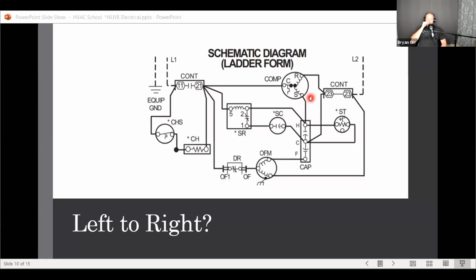In some cases, those resistances will be so low that your meter will actually ring when you're measuring leg to leg. And that doesn't mean that your compressor is always going to draw these ridiculously high currents. Because if you work Ohm's law, it will look like you're going to have 100 amps, whatever. That's only what it draws when it starts. Once that compressor gets moving and you get that inductive reactance, that's additional impedance, as we call it. It's additional electrical resistance that shows up once that motor starts running, once that inductance kicks in.